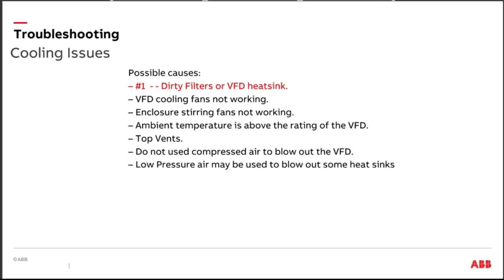The other thing is, if I open that door and I'm pulling the filter out, now I have the potential for dropping that filter, of putting more mess inside the cabinet. So make sure that if you're the specifying person, that you specify your filter kit to be applied outside of the door. Okay, and that'll save you a lot of issues there. Naturally, the cooling fans, you want to look at that.